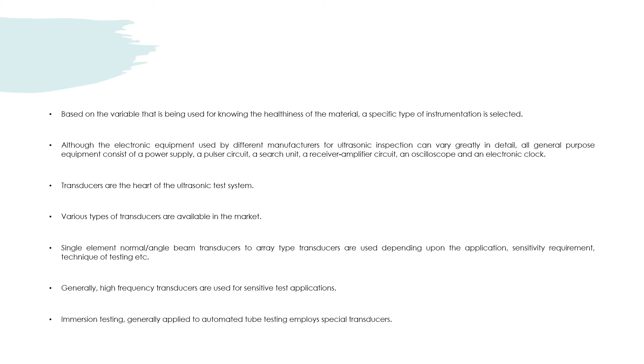Single element, normal or angle beam transducers to array type transducers are used depending upon the application, sensitivity requirement, and the technique of testing, etc. Generally, high frequency transducers are used for sensitive test applications. Immersion testing is generally applied to automated tube testing, employing especially shaped transducers.